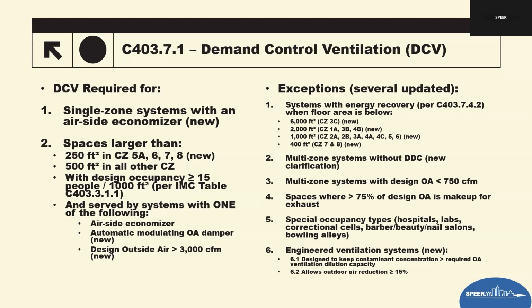This is having more stakeholders in those meetings to be able to align the requirements, as something else added to confusion in the 21. Other clarifications: multi-zone systems without direct digital control, the DDC, are exempt, since the DCV requires a DDC to function. 5, new engineered ventilation exception. A major addition to that is an engineered ventilation system designed by a registered design professional may be exempt if it can prove that contaminant levels would otherwise exceed allowable dilution rates, or outdoor air can be reduced by at least 15% without degrading indoor air quality. And then this gives engineers more flexibility on basically complex ventilation systems.